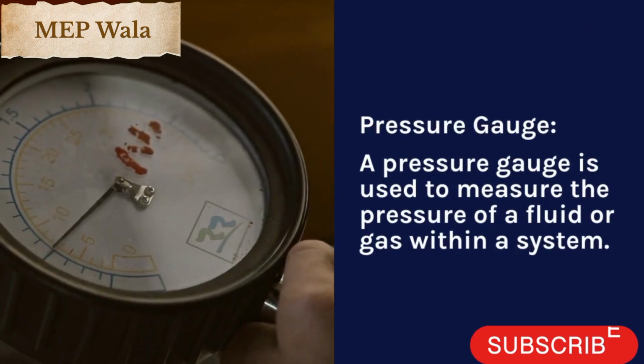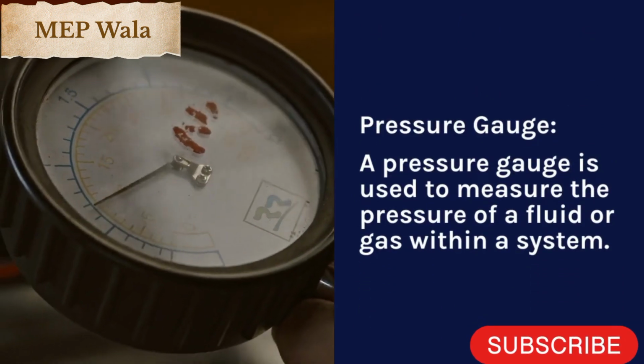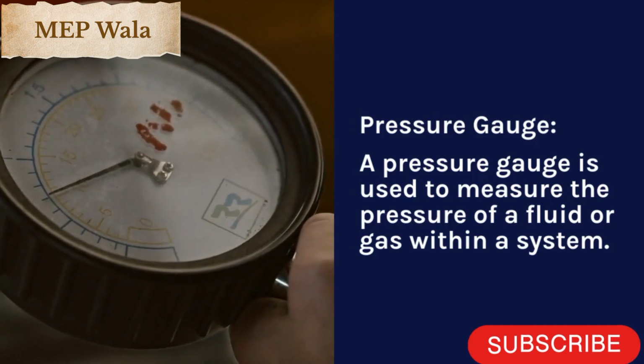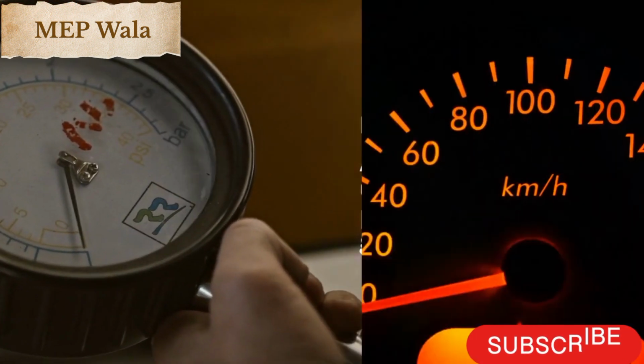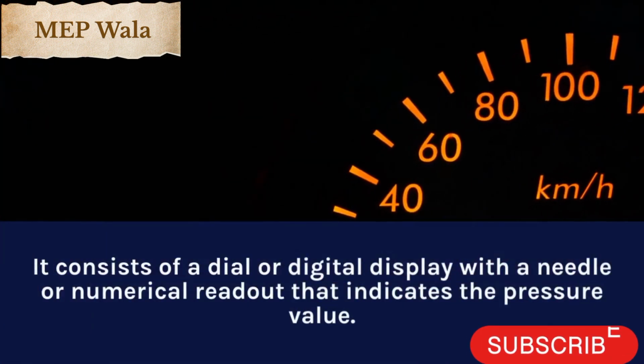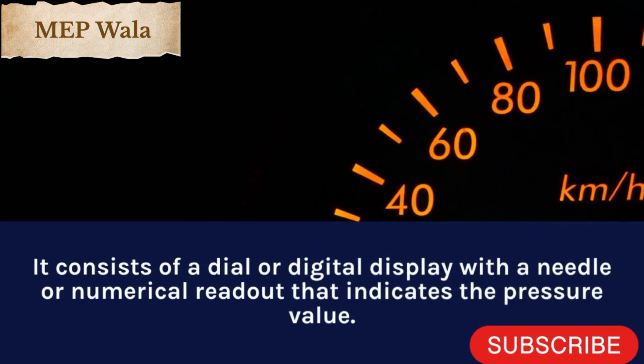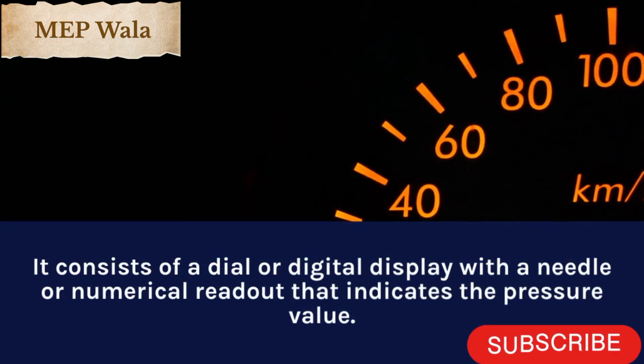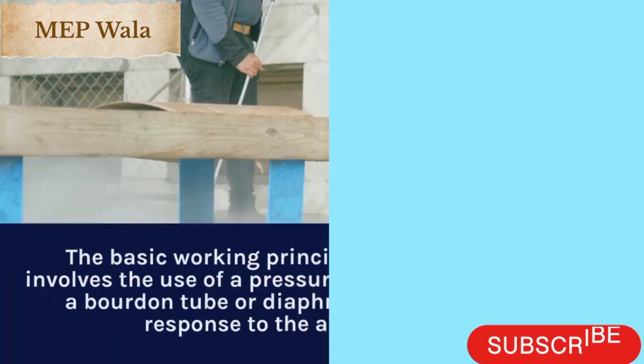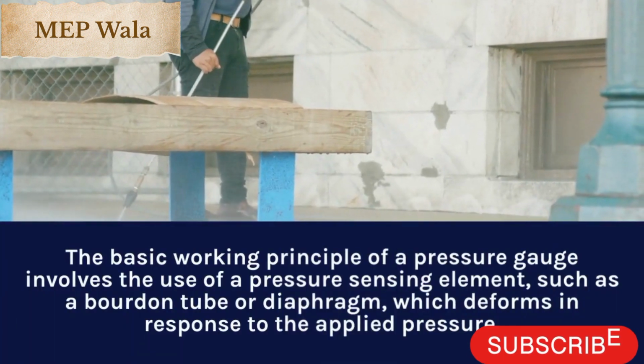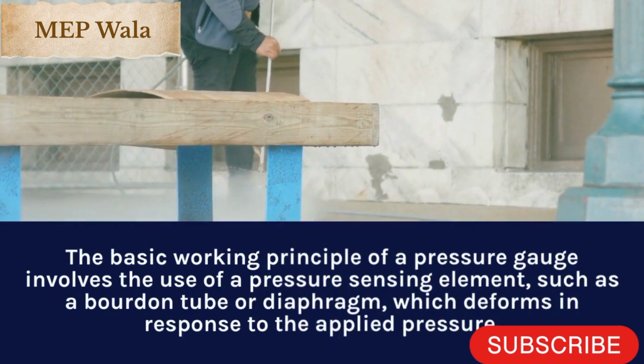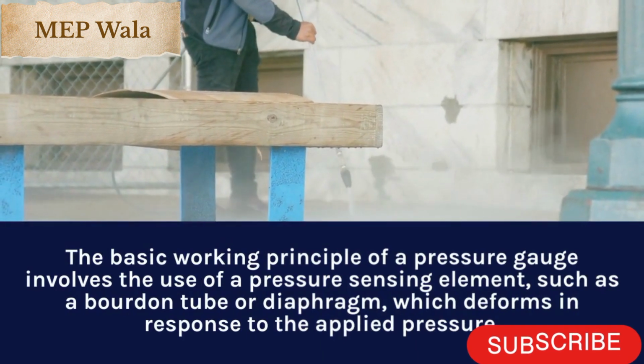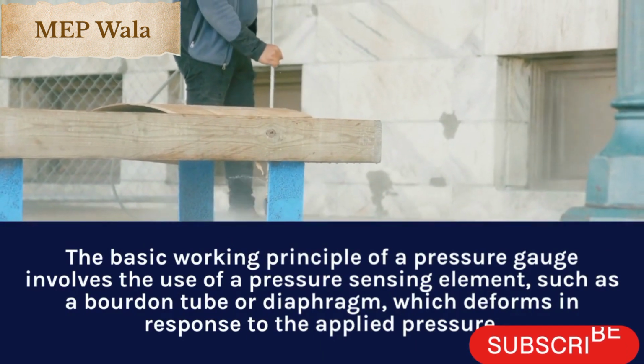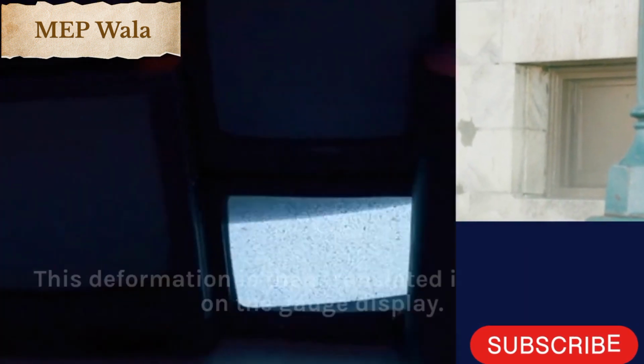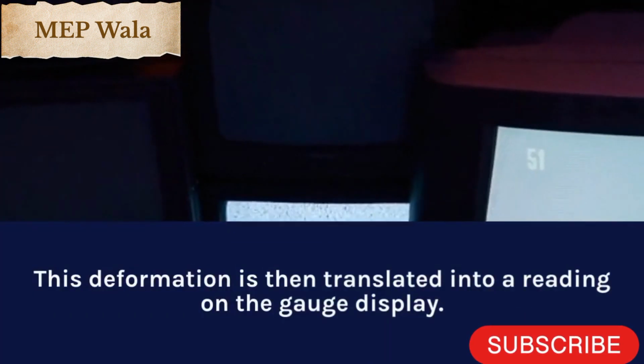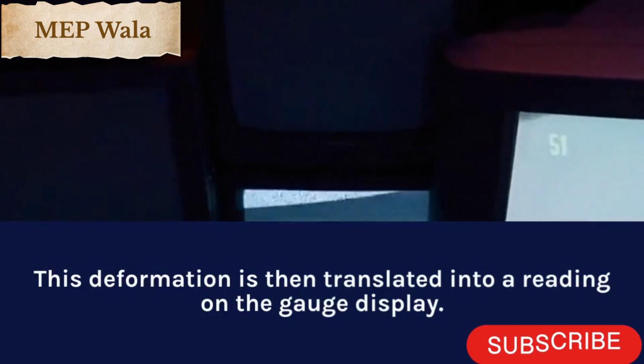Pressure gauge. A pressure gauge is used to measure the pressure of a fluid or gas within a system. It consists of a dial or digital display with a needle or numerical readout that indicates the pressure value. The basic working principle of a pressure gauge involves the use of a pressure sensing element, such as a Bourdon tube or diaphragm, which deforms in response to the applied pressure. This deformation is then translated into a reading on the gauge display.